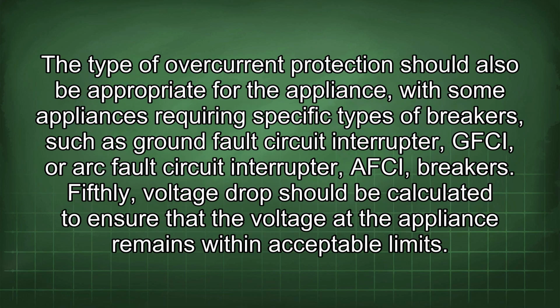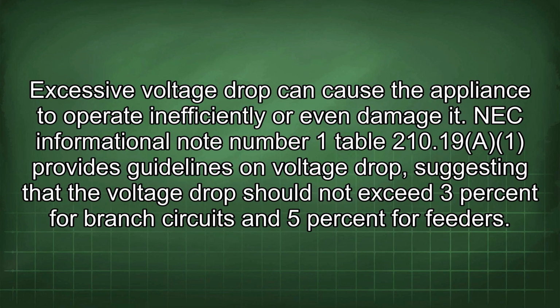The type of overcurrent protection should also be appropriate for the appliance, with some appliances requiring specific types of breakers, such as ground fault circuit interrupter, GFCI, or arc fault circuit interrupter, AFCI, breakers. Fifthly, voltage drop should be calculated to ensure that the voltage at the appliance remains within acceptable limits. Excessive voltage drop can cause the appliance to operate inefficiently or even damage it. NEC Informational Note Number 1 to Section 210.19(A) provides guidelines on voltage drop, suggesting that the voltage drop should not exceed 3% for branch circuits and 5% for feeders.